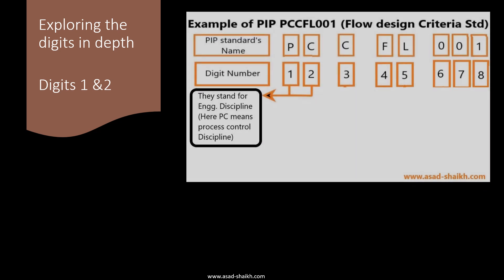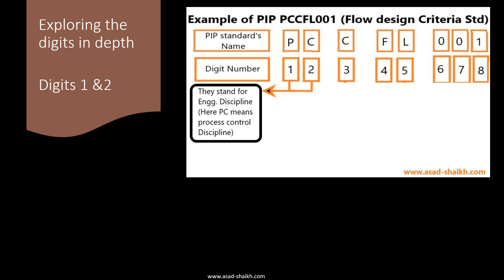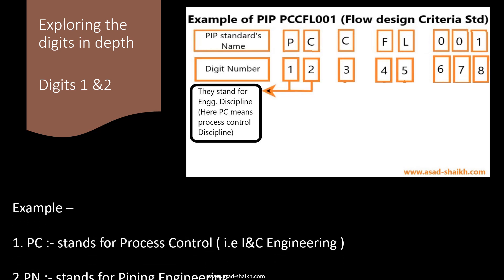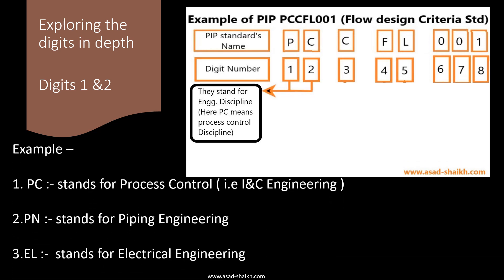The first two digits stand for the engineering discipline the standard caters to. For example, PC stands for process control — that is, instrumentation and control engineering. If the first two digits were PN, it would stand for piping engineering. EL stands for electrical engineering. Similarly, every discipline — project engineering, process engineering — has different digits representing that particular discipline.